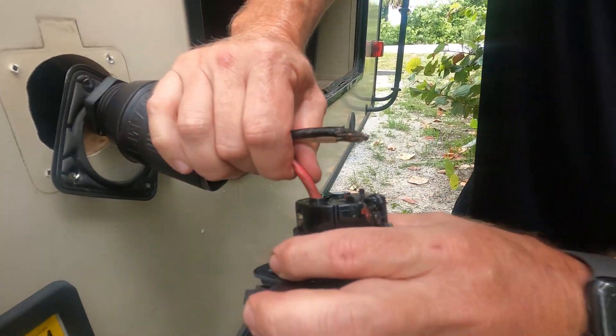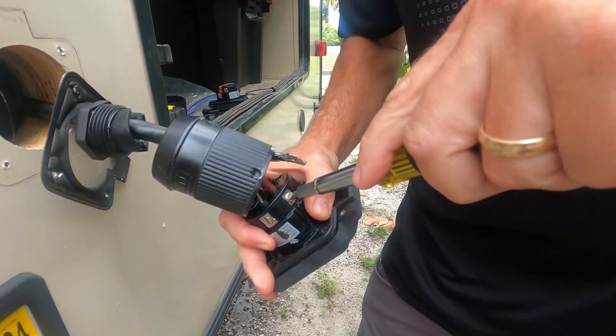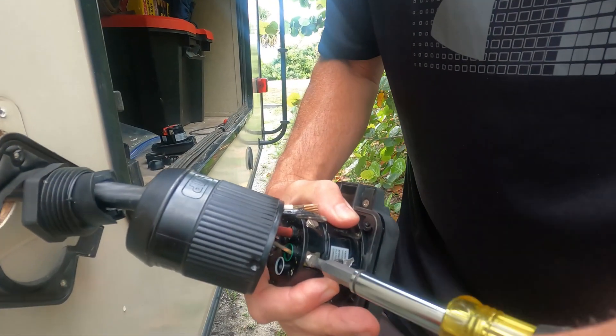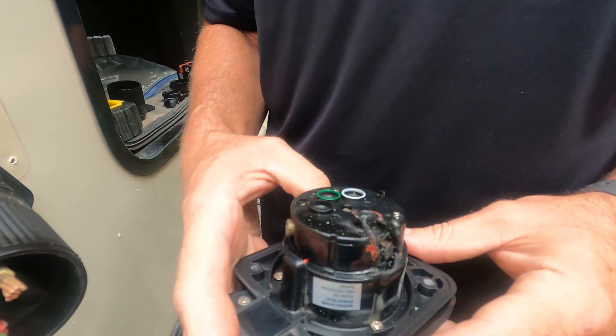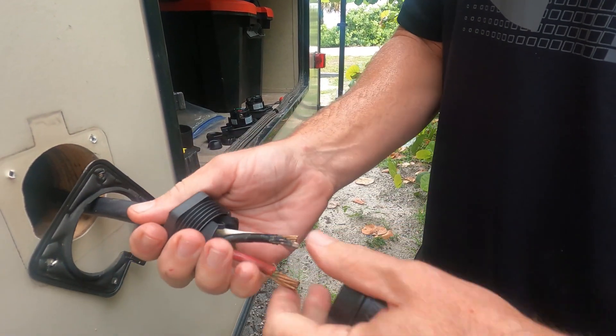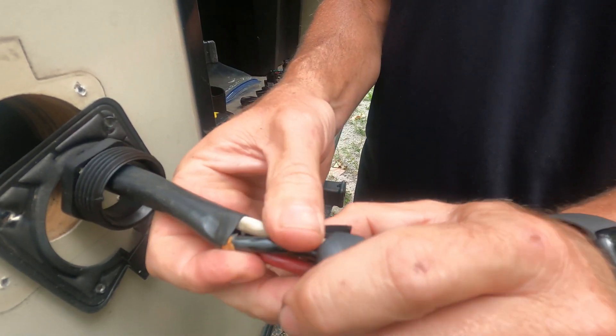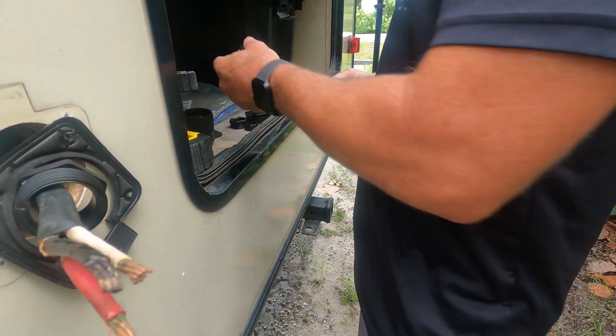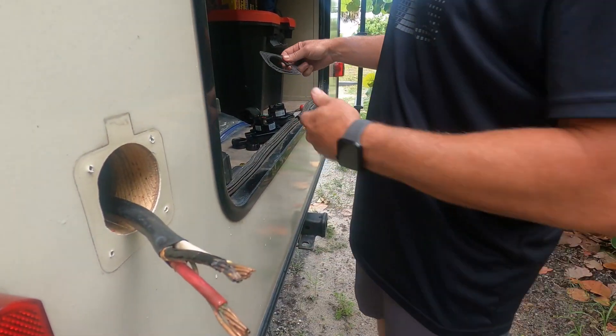So let's get the rest of these out. I'll be honest, that's actually pretty scary. This plug had some big problems — some big problems getting ready to happen. I'm going to take all this off. You can see the support they used was this clamp style here — it comes with a new one so I'll use that. We're going to get rid of all the old stuff, get rid of the old nut, everything.